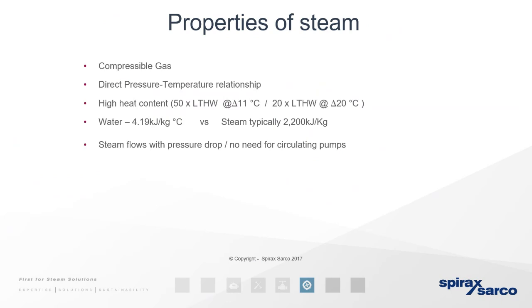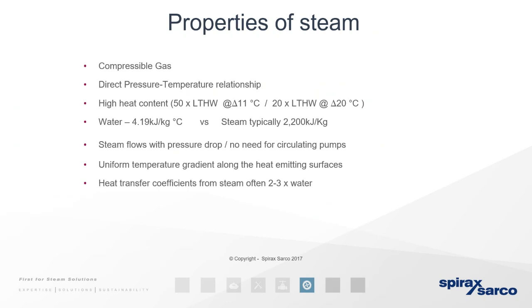Steam flows with pressure drop, and there's no need for circulating pumps, so it's what we call a pull system. By steam collapsing downstream and creating a vacuum, it pulls fresh steam from upstream in to fill the void, so there's no need for a pump. And a uniform temperature gradient, so we know how much heat it loses over a certain distance of pipework at a certain thickness, so it makes it very easy for us to calculate and work out the heat losses from your system. And the heat transfer coefficients are often 2 to 3 times higher than water. Again, talk about latent energy when it's condensing. So as the steam condenses, that's when it gives off its heat.